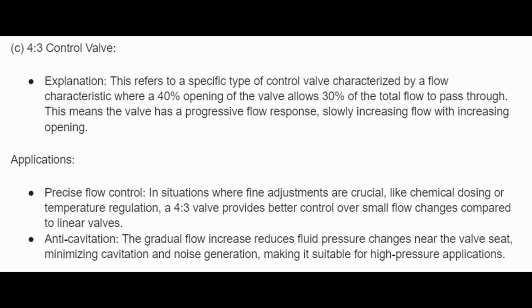C. 4-to-3 control valves. Explanation. This refers to a specific type of control valve characterized by a flow characteristic where a 40% opening of the valve allows 30% of the total flow to pass through. This means that the valve has a progressive flow response, slowly increasing flow with increasing opening.